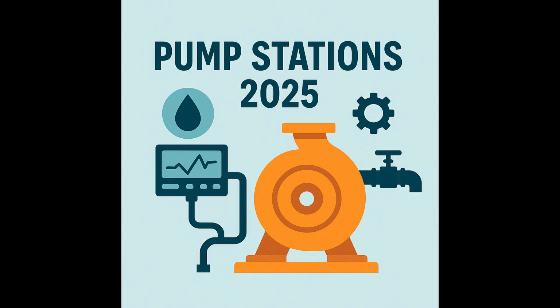And what drives that choice? The decision factors in the calculated minimum, average, and peak flows the station needs to handle, plus regulatory requirements for what's called firm capacity, meaning the station must still meet certain flow requirements even if its largest pump is out of service. Oh, okay. So it's always a balance between the initial capital cost, obviously. Fewer pumps are cheaper up front, and the required level of reliability or risk tolerance. More pumps generally mean more reliability but higher cost.